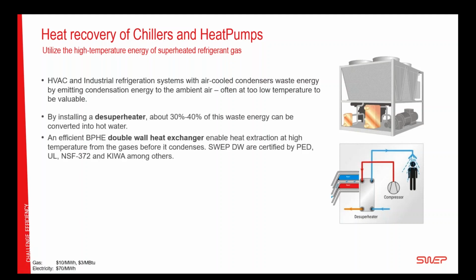However, if the desuperheater is installed, we can get about 30 to 40% of the condensing energy at a higher temperature. And by using a brazed double wall heat exchanger, it's possible to take this energy directly and run it against cold tap water coming in and having warm shower water, warm tap water directly. SWEP double walls are certified by PED, UL, NSF 372, and KIWA, among others, to use for tap water.